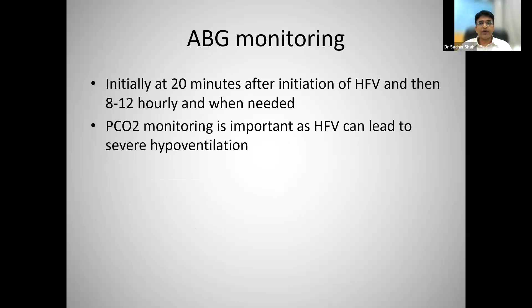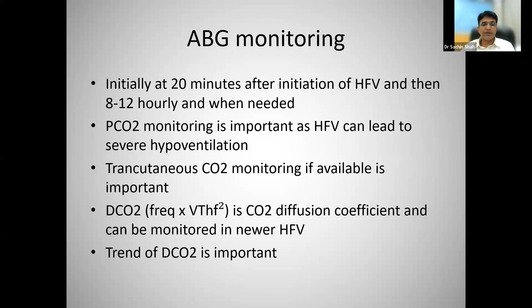As I told you, in newer ventilators you have carbon dioxide monitoring because you have tidal volume monitoring. So the DCO2 value you get, which is a carbon dioxide diffusion coefficient, can be monitored. It is not a direct correlation of the carbon dioxide levels in the blood, but it will give you a trend of what DCO2 you were on, and within the next few hours, whether it is increasing or decreasing, you will know the trend of carbon dioxide inside.